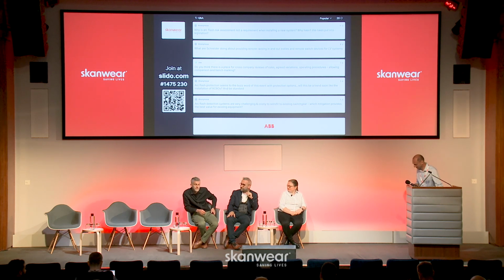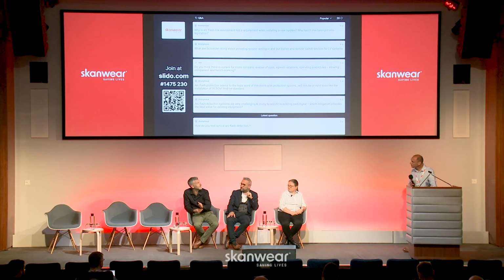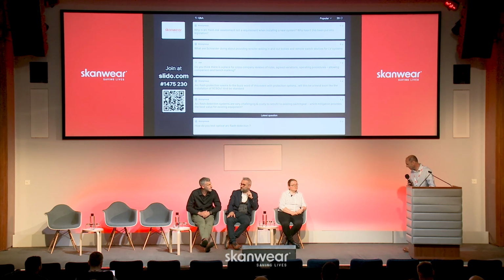My understanding was that if you installed new equipment from 2014 onward, it should have been supplied with an arc flash assessment; prior to that it didn't need to. So if you've got older kit, you'll have to go and get an external one, but if it was built from 2014 onwards the manufacturer should supply it as part of the design process. That's effectively its testing at that point, where it sits into your system, though incident energy levels are a completely different matter. It also differs between HV and LV, there isn't currently a requirement for LV to be arc flash rated, whereas there is for HV.